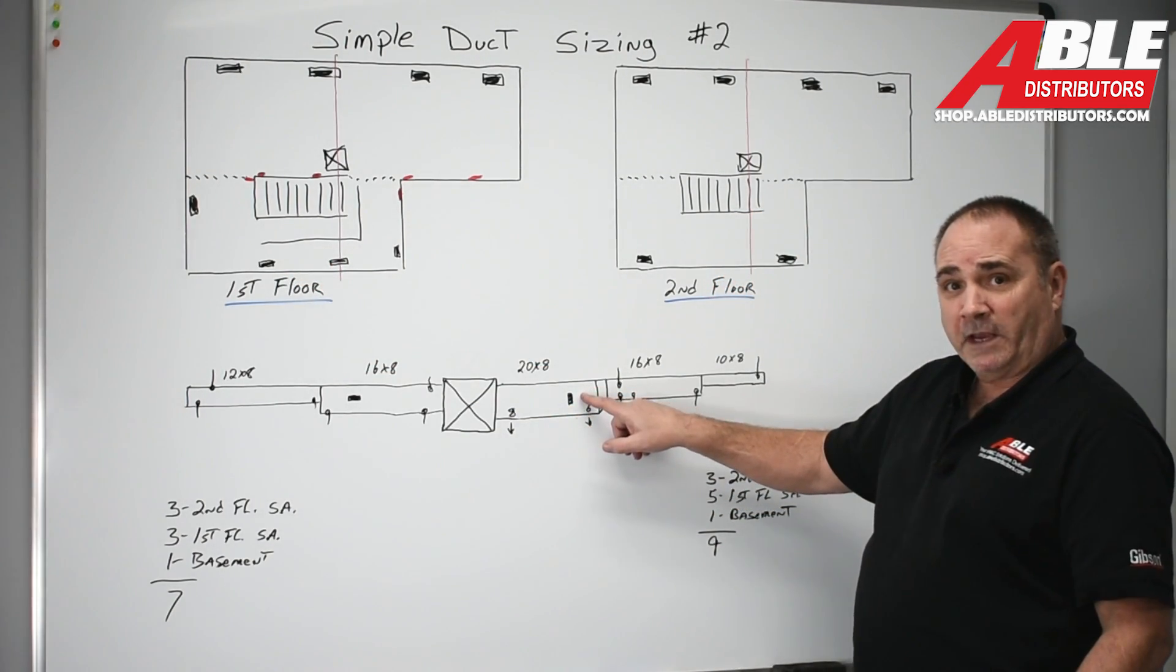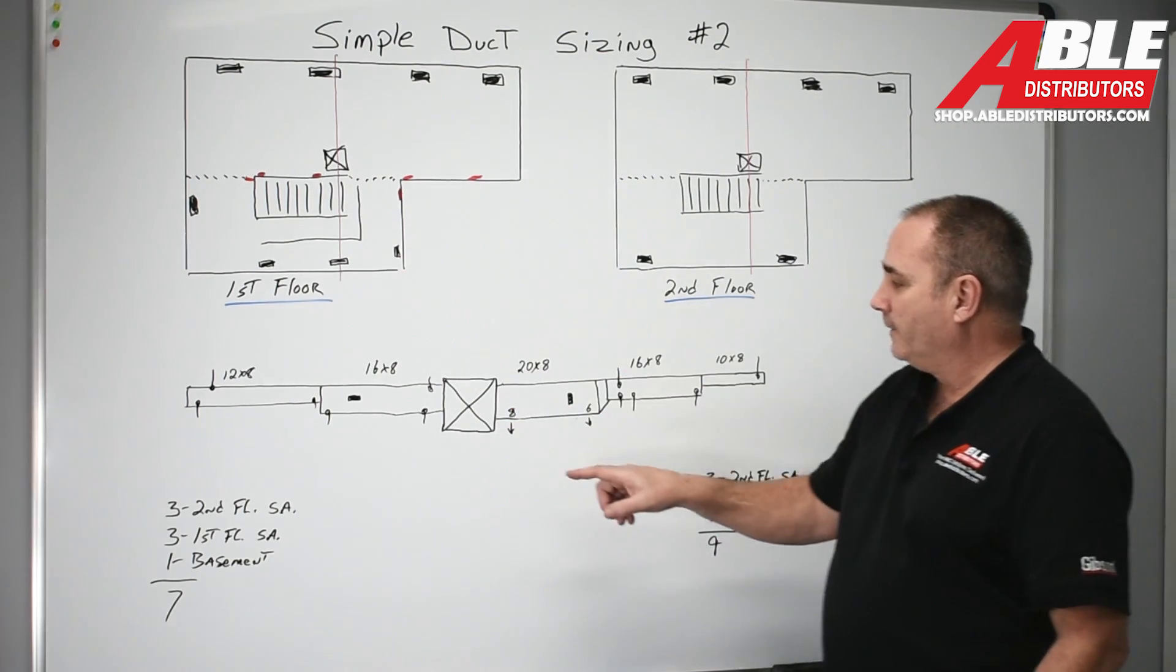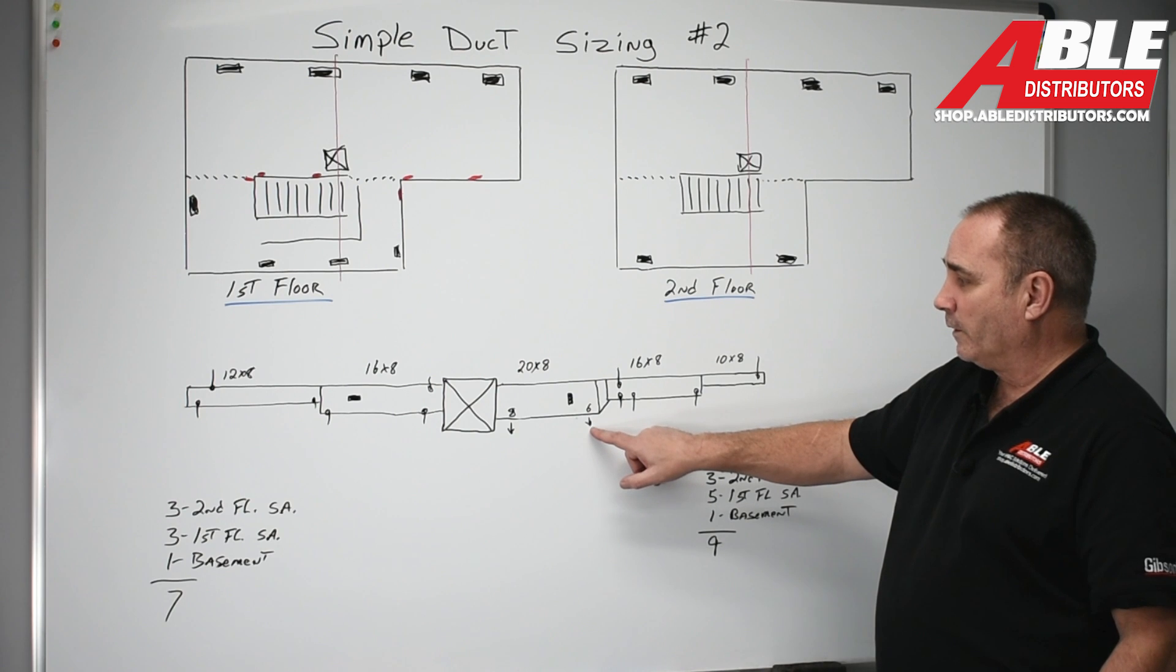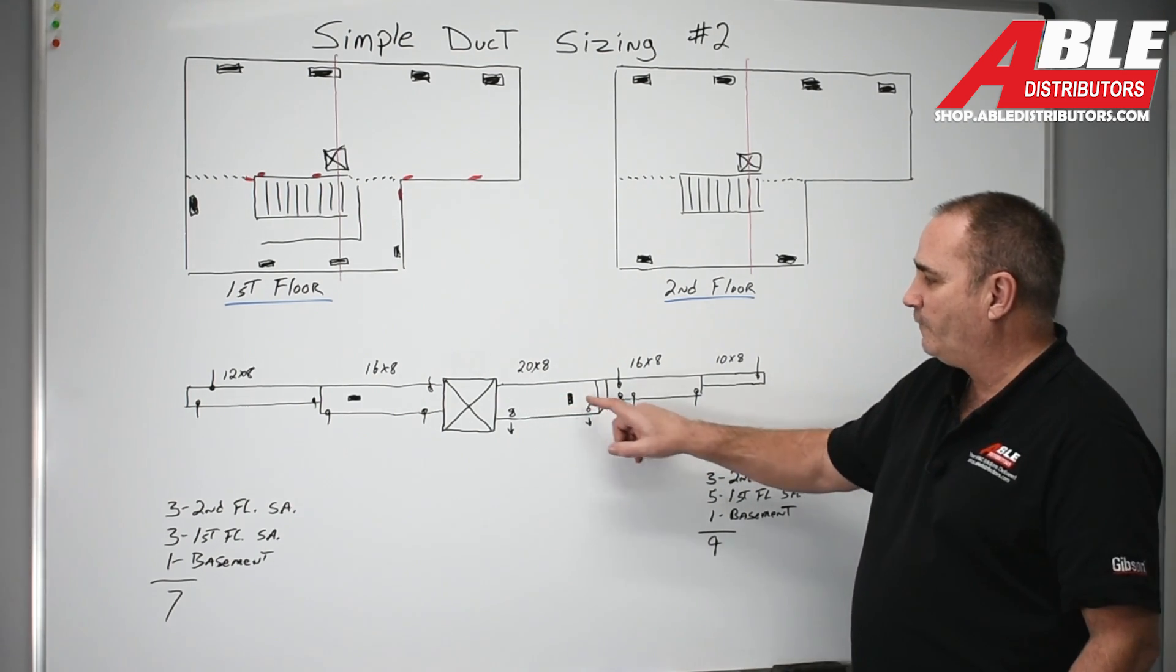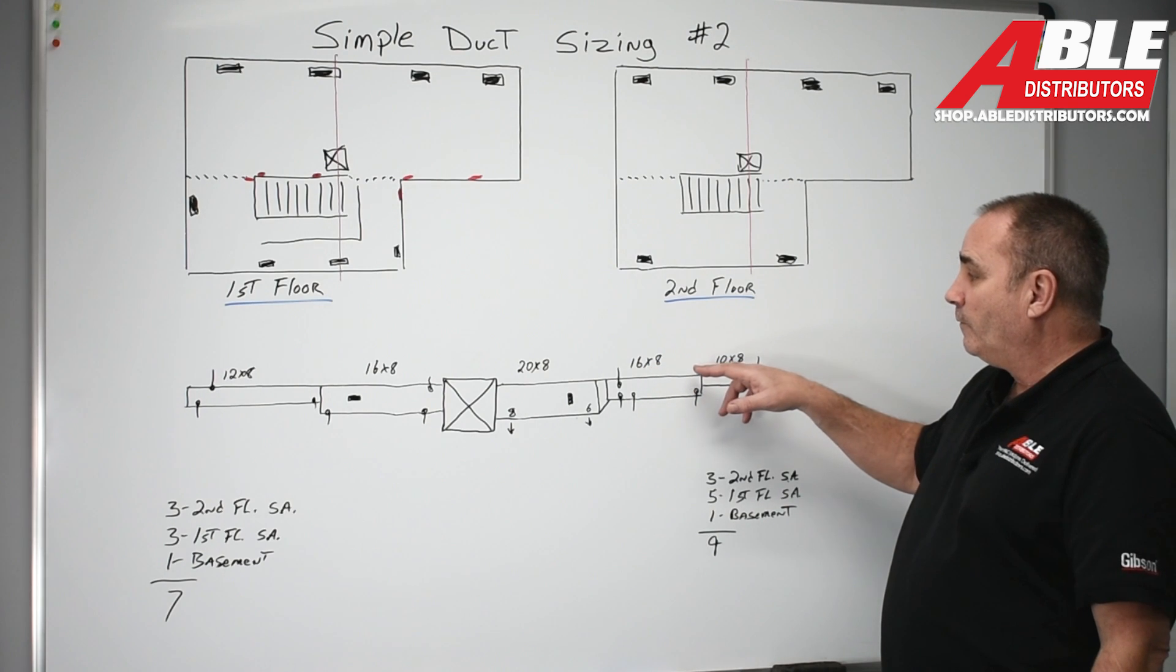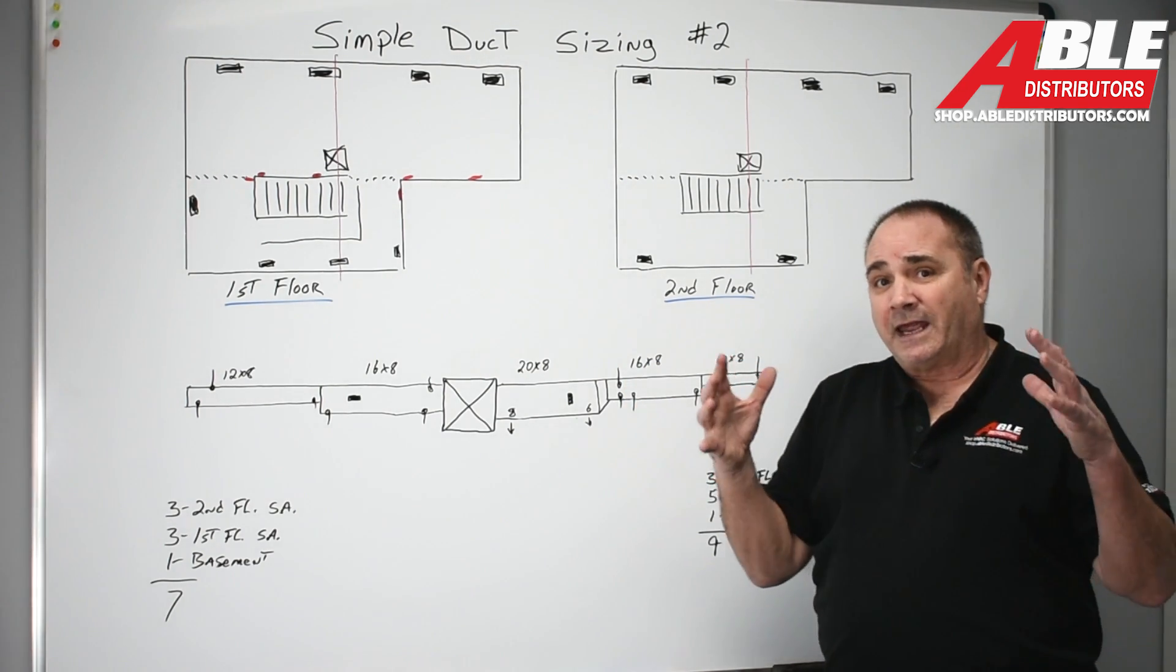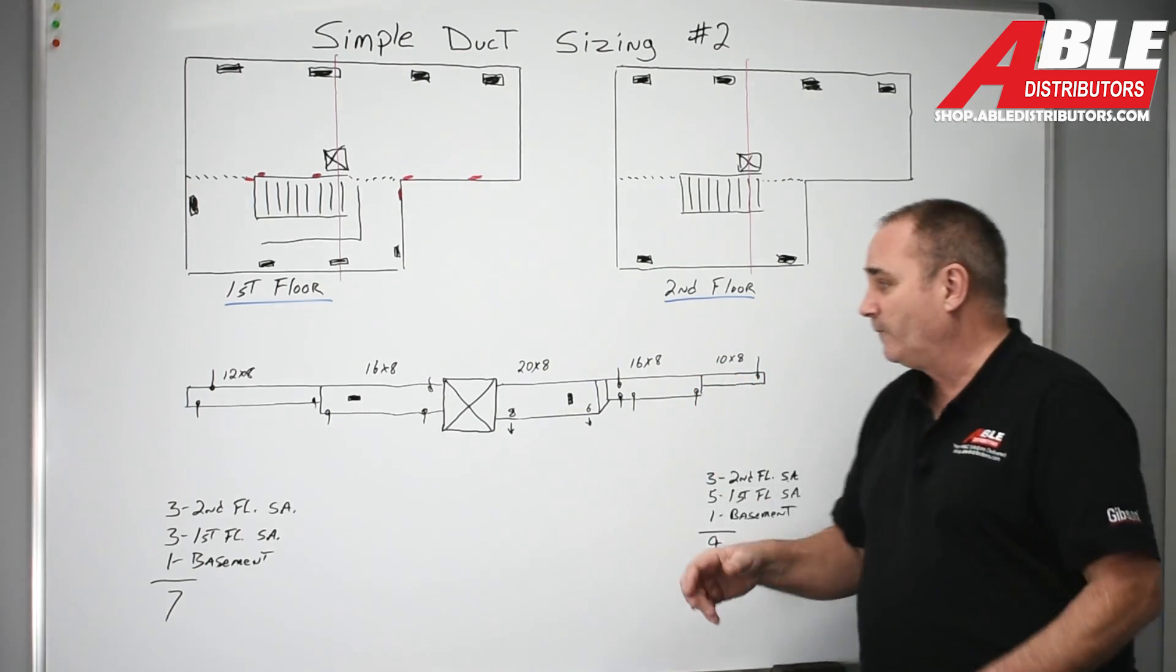I'm going to cut one in for the basement that's three and then I'm going to pick up this supply on the first floor that's four. So I've got one, two, three, four - four off of that. Now we reduce to 16 by 8 because again I've got four more so that duct has to be capable of 440 CFM.